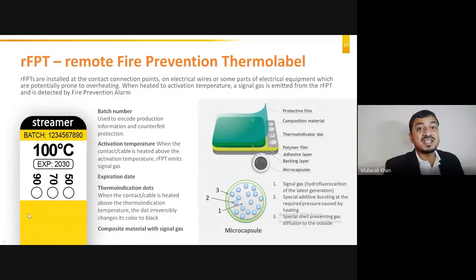When the temperature reaches 100 degrees Celsius, the signal gas will be emitted from the sticker and sensed by a gas sensor installed in the same cabinet. So these are the various indications: 50, 70, 90 are pre-alarms without any remote indication, only visual and local, with an irreversible change. At 100 degrees Celsius, signal gas is emitted and it gives you a remote alarm. That is the function.